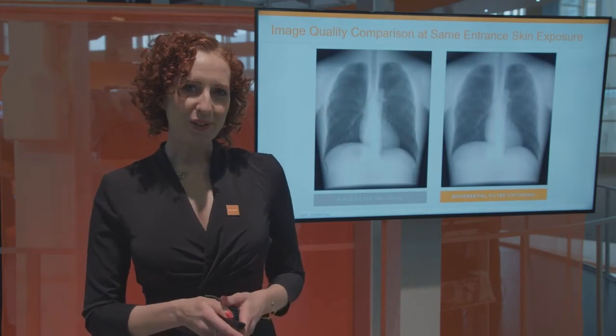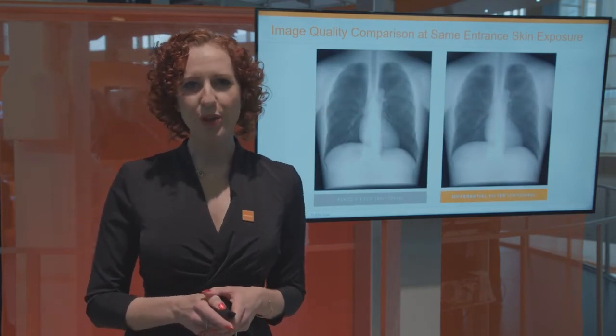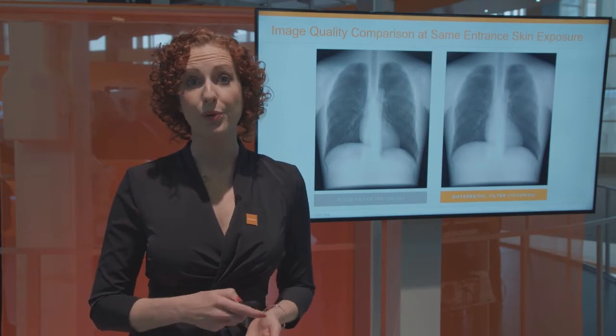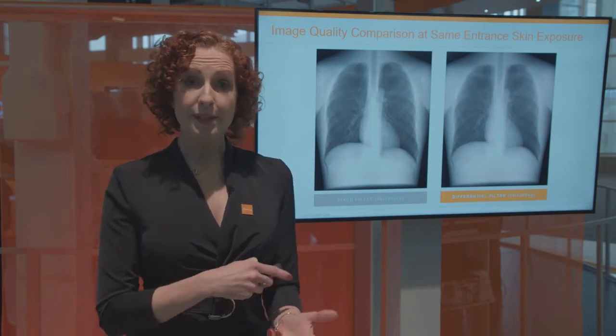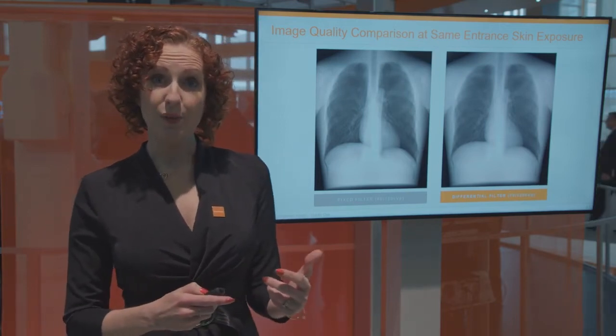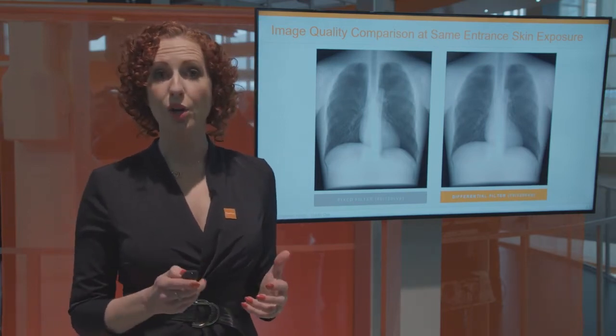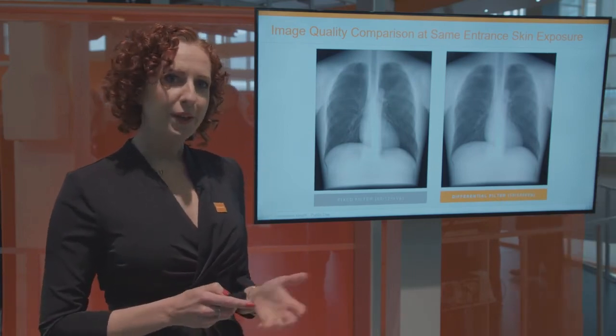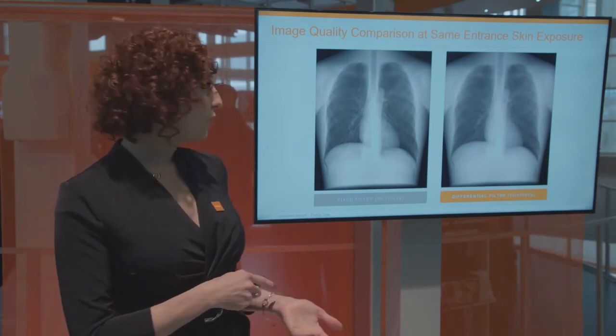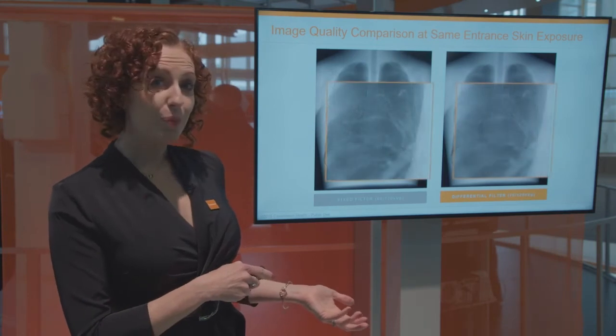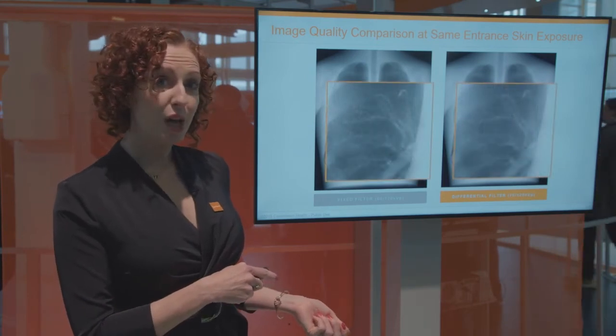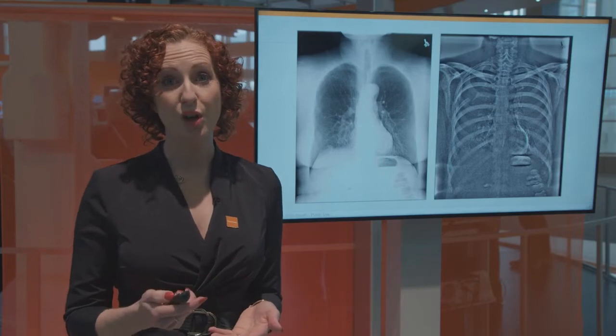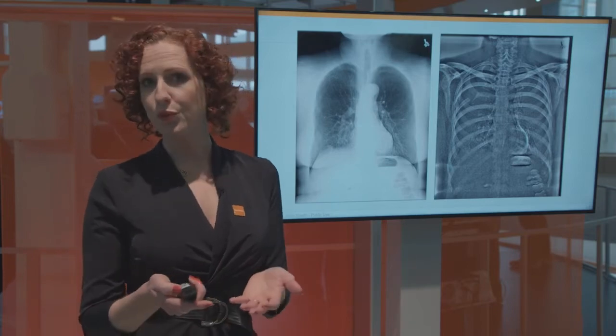By comparison, CareStream dual energy image quality is far superior when compared to the conventional approach. The time interval between the successive acquisition of the high and low-energy image pair is about one quarter of a second. But even with this rapid sequence, a slight degree of blurring can sometimes be seen at the reconstructed soft tissue and bone images' linear edge structures, such as rib cages.